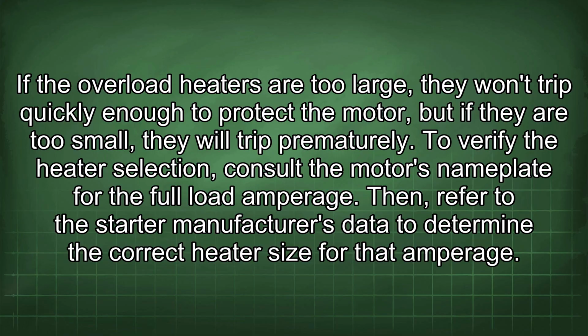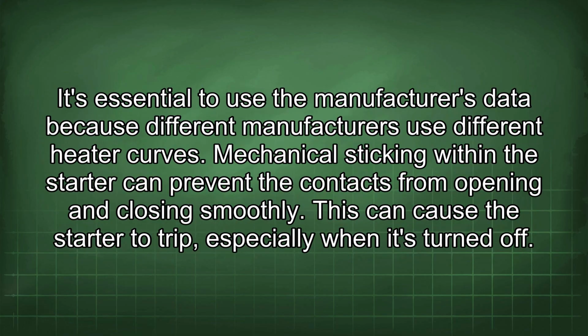To verify the heater selection, consult the motor's nameplate for the full load amperage. Then, refer to the starter manufacturer's data to determine the correct heater size for that amperage. It's essential to use the manufacturer's data because different manufacturers use different heater curves. Mechanical sticking within the starter can prevent the contacts from opening and closing smoothly. This can cause the starter to trip, especially when it's turned off.